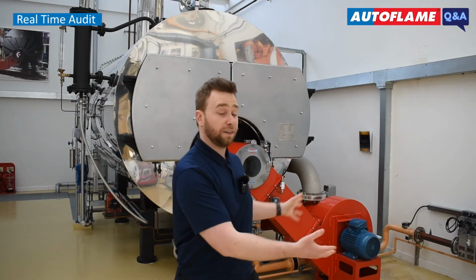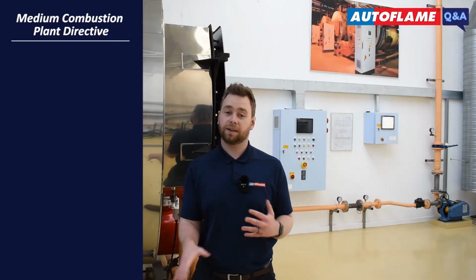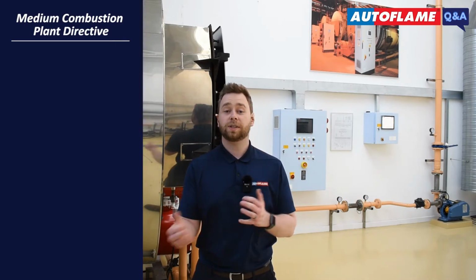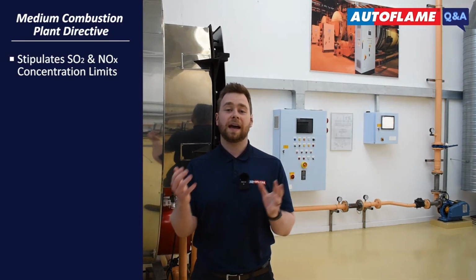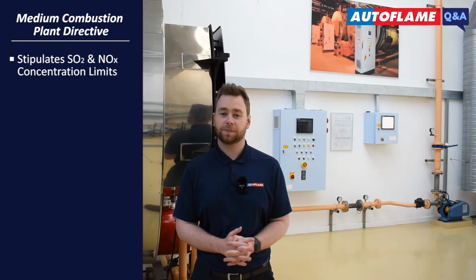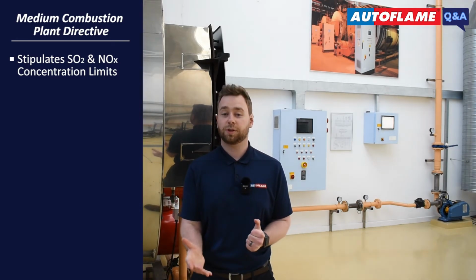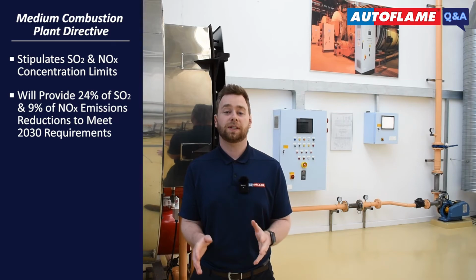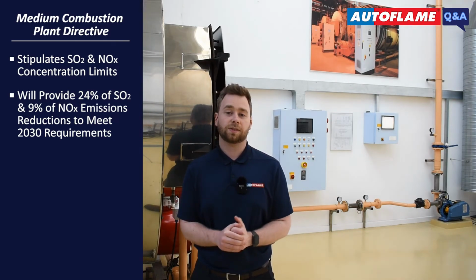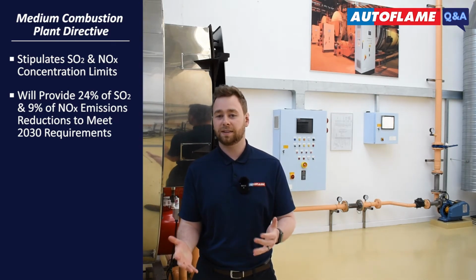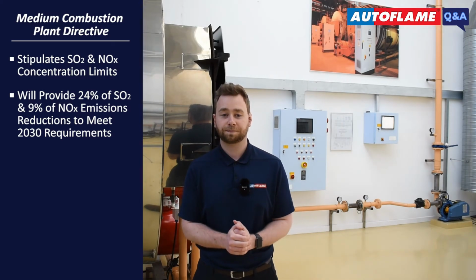This valuable data, in combination with the amount of fuel being burnt, presents a complete picture of how efficiently that burner has been commissioned. For example, in the UK, we must now conform to the MCPD, or the Medium Combustion Plant Directive, which stipulates predominantly SO2 and NOx concentration limits. This UK-wide implementation of these restrictions will provide an estimated 24% of the SO2 and 9% of the NOx emissions reductions needed to meet the UK's 2030 requirements.